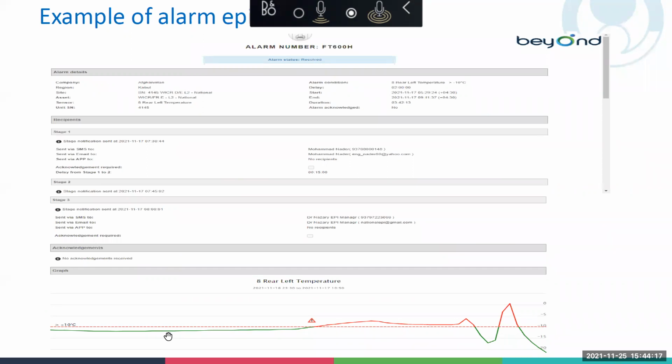Immediately this was sent, action was initiated, and the technicians were sent to find out what the problem was, because the machine was showing that the temperature reading was not going below -10 degrees centigrade. They observed that the cooling unit was malfunctioning, so they replaced the cooling unit immediately because we have a stockpile of spare parts for this equipment. After the issue was resolved, the equipment started working perfectly.